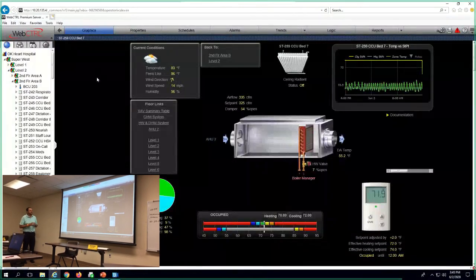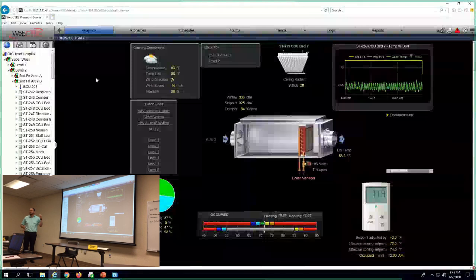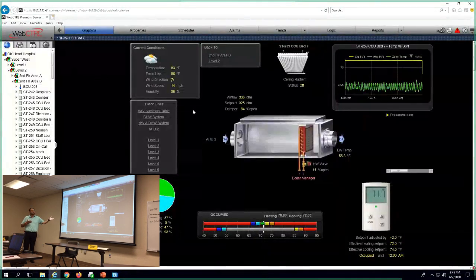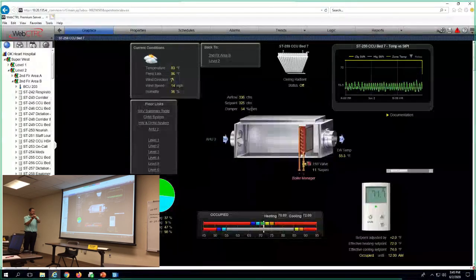One of the things we try to do is to keep the screen as simple as possible, so you can look and see, is it doing simply what you need to know? Is it doing what it's supposed to do? If the space is showing up orange, red, dark blue, click on it and we can figure out what's going on. Number one, is it maintaining the airflow set point? Yes, it is. Its set point is 325 CFM. The actual airflow that we're measuring is 336.